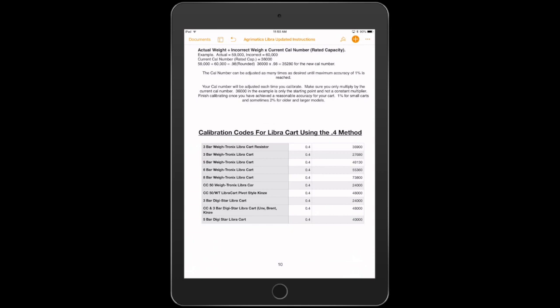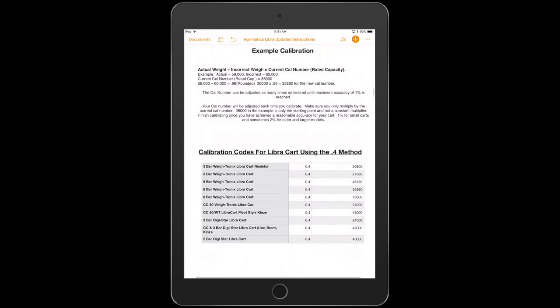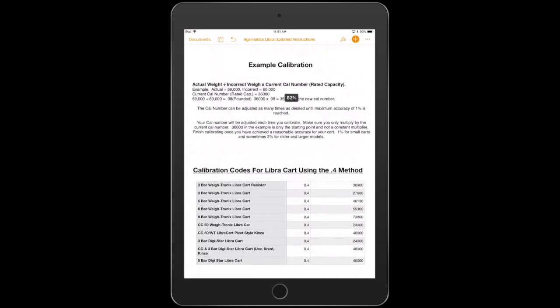But if you see any of these numbers input onto the Libra box, there is a sticker, and we will have the calibration written on there, so that way you have a starting point. So if you go through, you've got the 3-bar Weigh-Tronix, 5-bar Weigh-Tronix, 6-bar, 8-bar, the compression cells, they're all on there. Digistar is listed on there as well, 5-bar carts, and these will get you to where you need to be, and then you might need to do a little bit of adjustment by following this formula right up here.